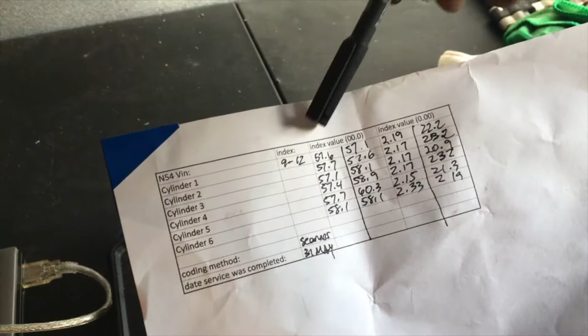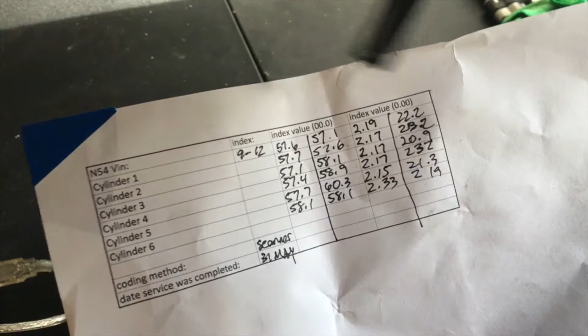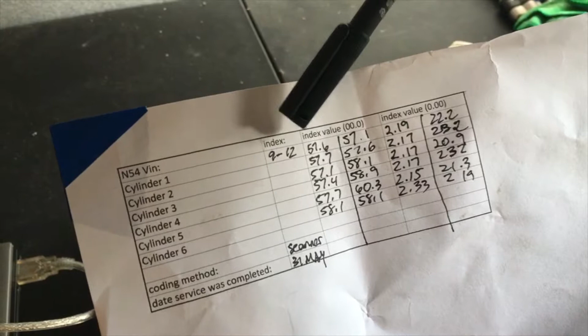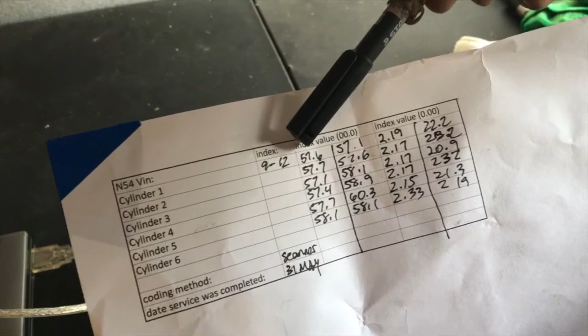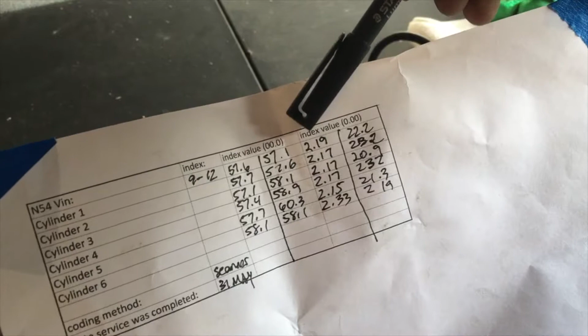Okay, so as you see here, I have index value with a 00.0. So that's going to be your larger number. Your first number on that left-hand side is going to be XX.X. So in this case, our index value is 57.6, the calibration value. And then for the secondary value, or the one underneath it, the smaller value, is going to be 0.00 or X.XX. And in this case, it's 2.19. So let's get to it.